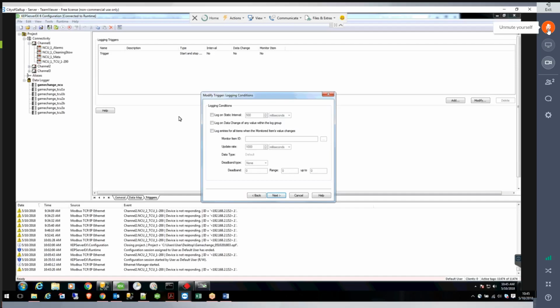And if we just click log on static interval here and click 5 and then minutes, we're not going to be guaranteed that data is going to log on the 5 minute data point every 5 minutes. So we want every minute. Yep. And the aggregations on Locus will do a pretty good job of making that smooth and easy to look at.